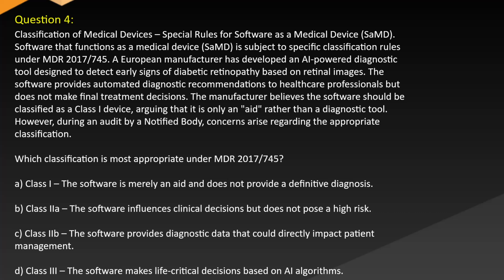The manufacturer believes the software should be classified as a Class I device, arguing that it is only an aid rather than a diagnostic tool. However, during an audit by a notified body, concerns arise regarding the appropriate classification. Which classification is most appropriate under MDR 2017/745? A. Class I. The software is merely an aid and does not provide definitive diagnosis. B. Class IIa. The software influences clinical decisions but does not pose a high risk. C. Class IIb. The software provides diagnostic data that could directly impact patient management. D. Class III. The software makes life-critical decisions based on AI algorithms.